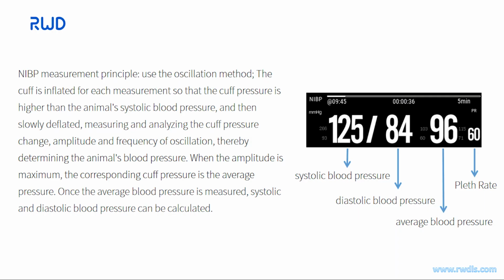The NIBP measurement principle uses the oscillation method. The cuff is inflated for each measurement so that the cuff pressure is higher than the animal's systolic blood pressure, and then slowly deflated, measuring and analyzing the cuff pressure change, amplitude and frequency of oscillation, thereby determining the animal's blood pressure. When the amplitude is maximum, the corresponding cuff pressure is the average pressure. Once the average blood pressure is measured, systolic and diastolic blood pressure can be calculated.